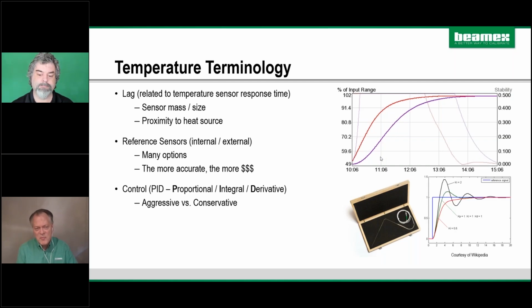Also, whether it's a bath or a dry block, there's a control algorithm going on, and everybody's using PID, proportional integral derivative style control. Over on the right is a step change where you're going from one temperature to another, and using PID parameters, you can have an aggressive type control where you overshoot but then come right back in, like this sine wave, or the red line's a more conservative approach where you approach the temperature. So typically with a dry block, you want your sensors to ramp up and approach the temperature. You're not wanting to necessarily overshoot.